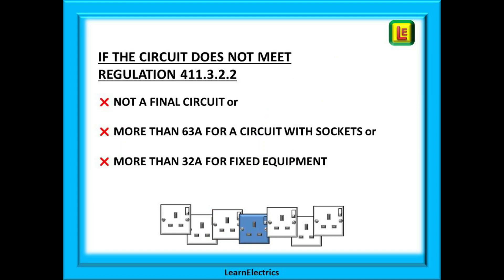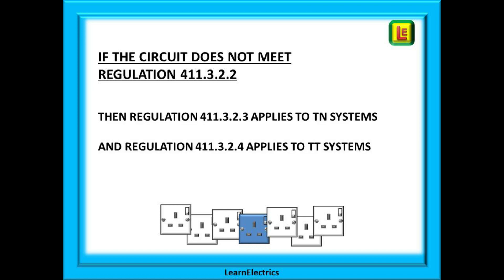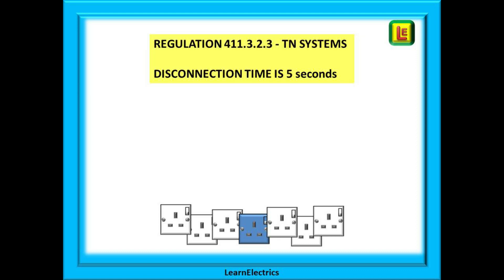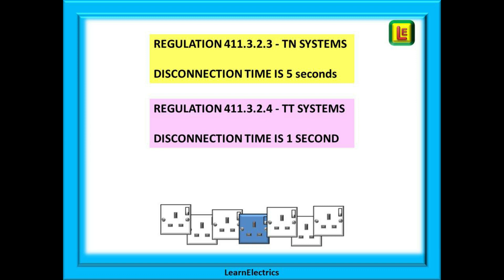Now we can look at circuits that do not meet regulation 411.3.2.2 — the circuit is not a final circuit, or it is a circuit with a socket greater than 63 amps, or it is a circuit for fixed equipment greater than 32 amps. In this case the disconnection time is straightforward. If it is a TN system, regulation 411.3.2.3 applies. Regulation 411.3.2.3 for TN systems tells us the disconnection time is five seconds regardless of the voltage.